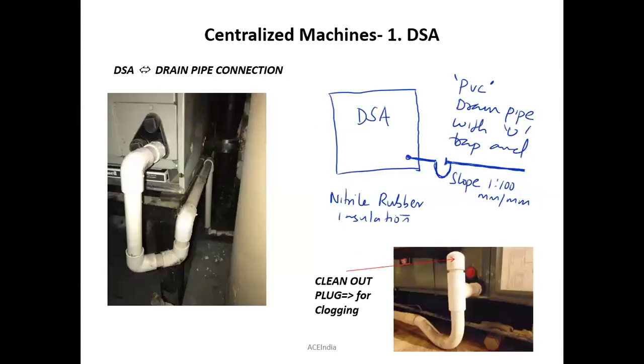Okay, now later it's about the drain pipe connection. Fair enough, we have covered the major topics of the DSA. We know that when the return air and fresh air, which contain moisture, come in contact with the evaporator coil, there will be some water droplet formation, isn't it? Those water droplets are collected with the help of a drain pan, and later rejected through a pipe, and the pipe material should be CPVC. Nowadays they use CPVC pipelines, not PVC: chlorinated polyvinyl chloride.